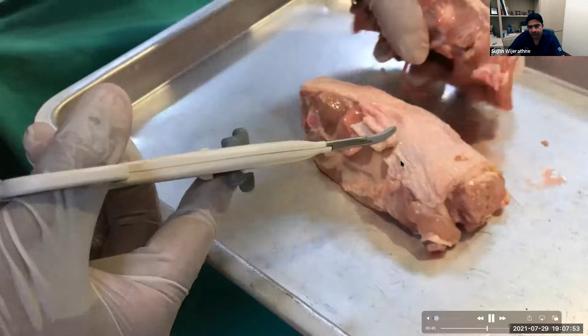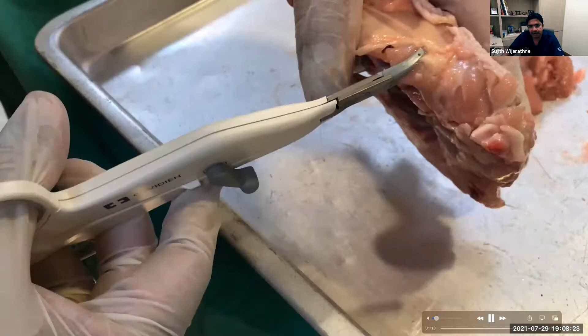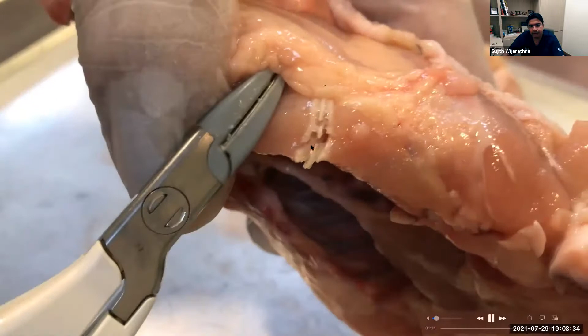You can see, compared to the ultrasonic, the amount of lateral thermal damage and the residual heat. This is ultrasonic and this is bipolar. The thermal damage seems to be slightly less in bipolar. It does have continuous feedback, at least about 200 times per second, into the machine about tissue impedance. This is how it recognizes. This is without cutting. You can see the amount of tissue damage.